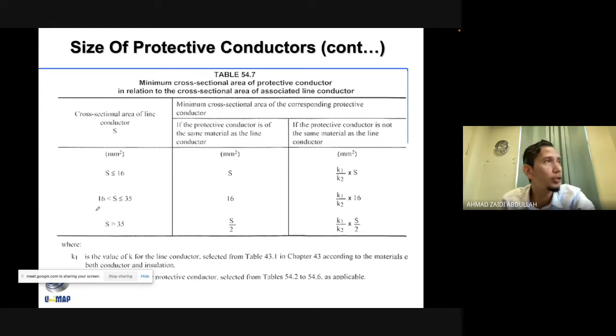Sama lah macam ni. Macam, let's say phase S to phase lah. Okay. Katakan phase tu maksud kabel live kamu, kabel red ke, yellow ke, blue ke. Your calculation adalah katakan kamu dapat 10 mm. So size of earthing kamu adalah follow saja. Follow saja. Katakan phase red kamu 10 mm size. So your earth cable just follow 10 cable. Itu je, macam tu je, senang. So directly follow, if the phase conductor is below than 16.